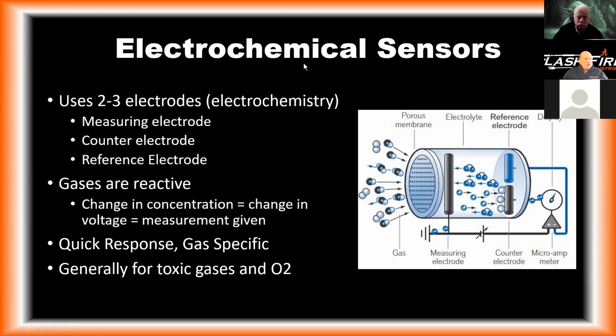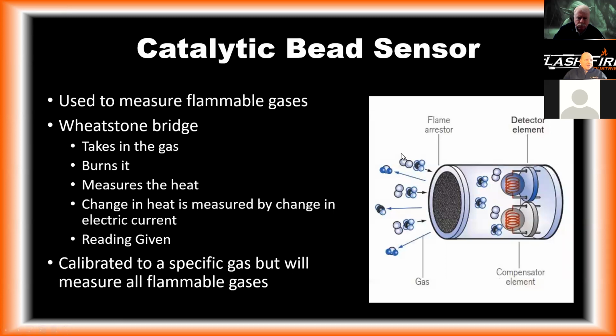So the advantage of these electrochemical sensors, and this is what would be used on CO, hydrogen sulfide, hydrogen cyanide, and O2 as well, is that it's a quick response and it's gas specific. So for the most part, though, there are cross sensitivities that we'll talk about, you're only reading the gas that you want to read. Whereas when we talk about LEL, you could be reading a variety of different gases. Any flammable gas will register on the LEL sensor.